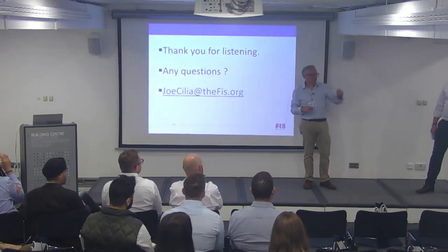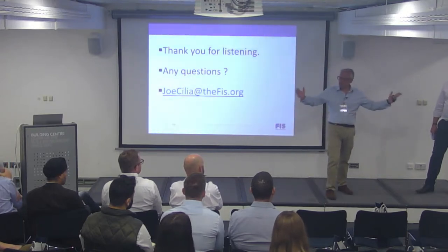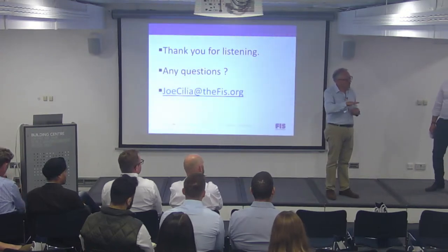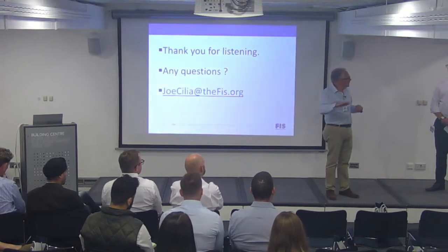You did a test and you got a class one. You had another test with class one. You put those two things together. You got what industry called class 0. It was a reaction to fire. It was about a surface spread of flame.